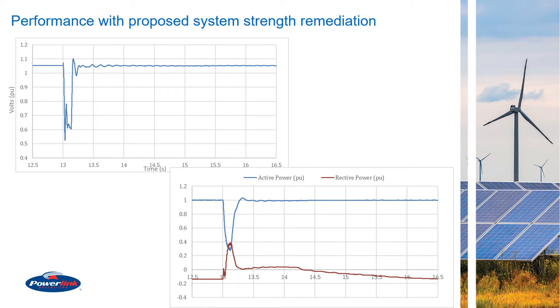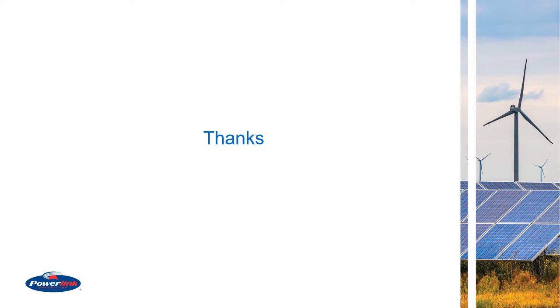Once the generator proposes the system strength remediation, simulations are rerun and the plant's performance is reassessed with the proposed remediation. What we see here is that after the fault recovery, oscillations are well damped and the sustained oscillations that were previously observed are not there. This proves that the remediation proposed by the generator was able to mitigate the adverse system strength impact. At this stage, the proposed remediation becomes part of the generator performance standard or GPS, and the application to connect progresses. And this brings my presentation to an end.